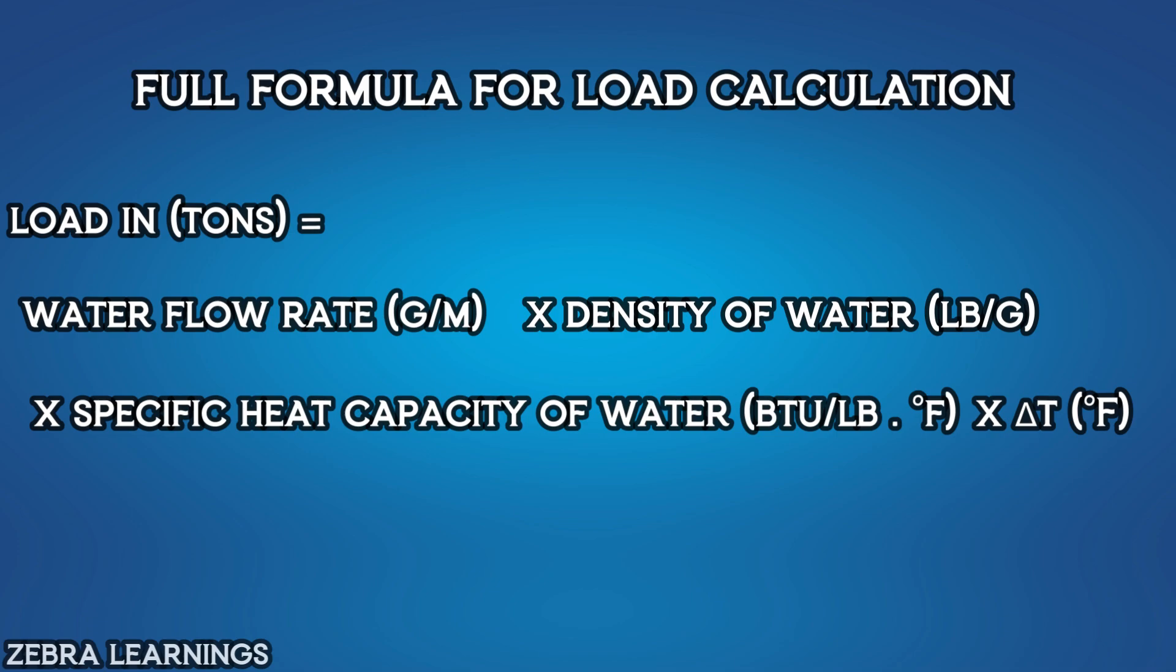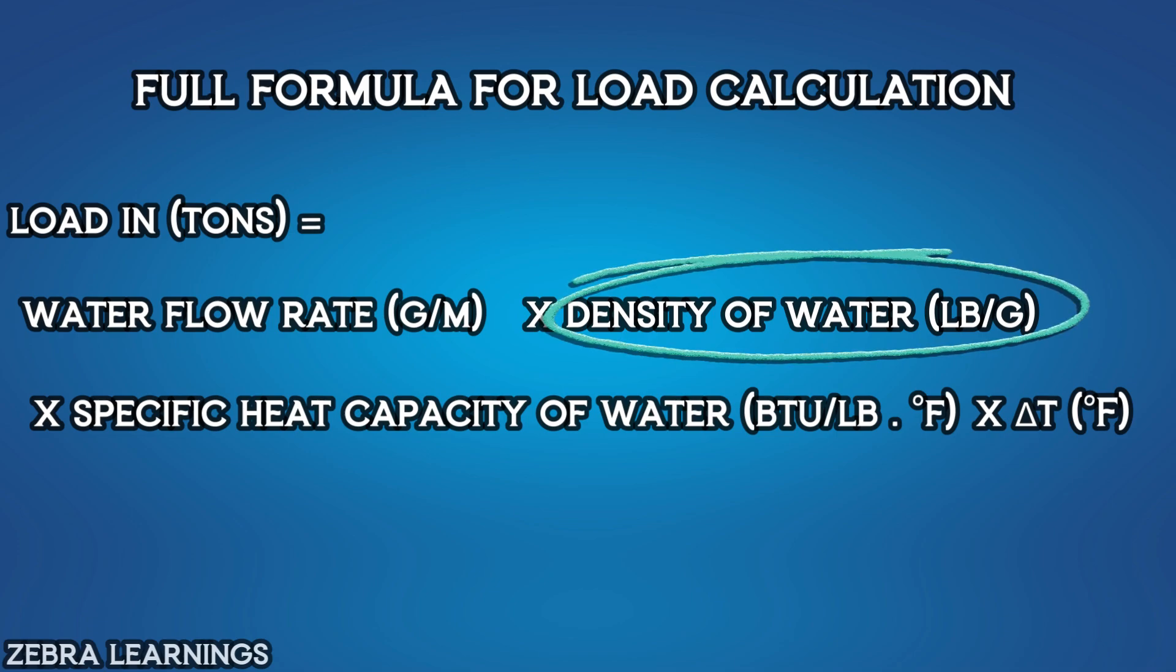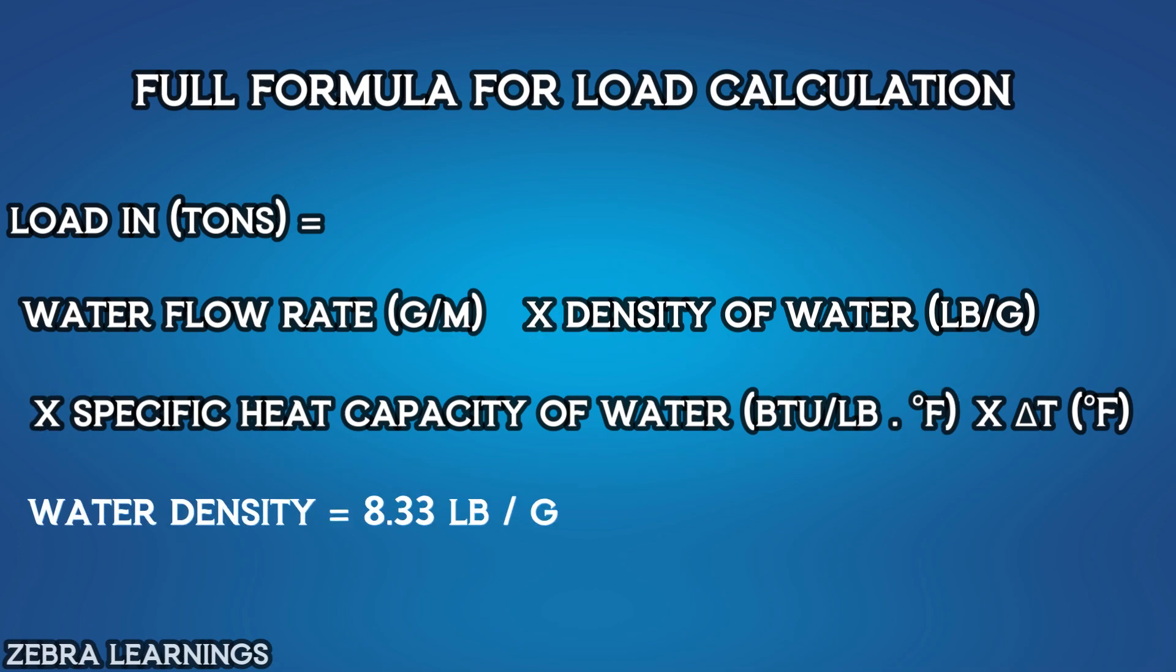Now let's simplify this formula. In this formula, we already know the values for water density and water specific heat capacity. Water density is 8.33 pounds per gallon, and water specific heat capacity is 1 BTU per pound degree Fahrenheit.